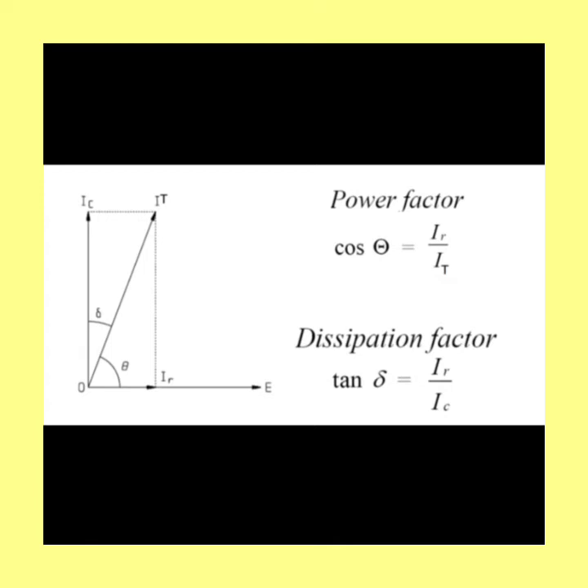The more leakage current, the more resistive current is there that will give direct impact on the tan delta value. As depicted in the equation, more resistive current means more tan delta, and that is the indication of deterioration of your insulation.